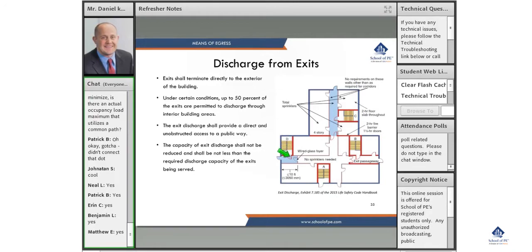And then with D, you go out here and you're in a protected vestibule, and then you can easily go out the exit to the exterior door. With A, the stair discharges directly to the exterior of the building, but B does not. We need B to discharge directly to the exterior because we already have the other two — we can only have 50% — so they connect it with an exit passageway. The idea is we go from one exit enclosure into another equivalent exit enclosure, and that leads us to the exterior of the building.